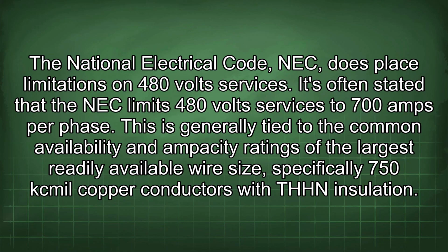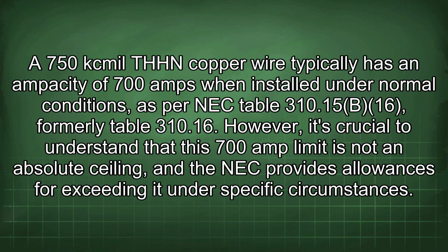The National Electrical Code, NEC, does place limitations on 480-volt services. It's often stated that the NEC limits 480-volt services to 700 amps per phase. This is generally tied to the common availability and ampacity ratings of the largest readily available wire size, specifically 750 kcmil copper conductors with THHN insulation.